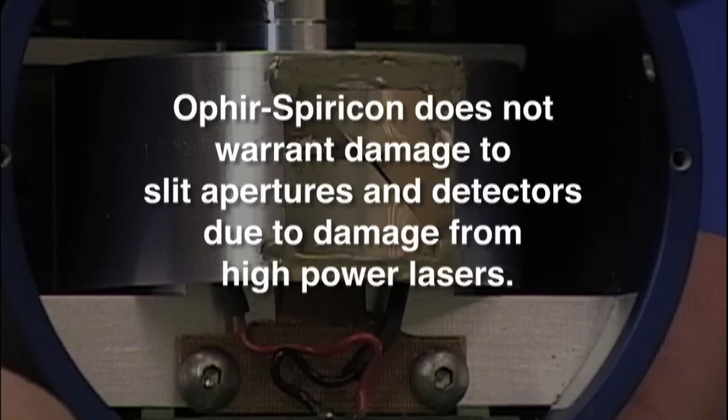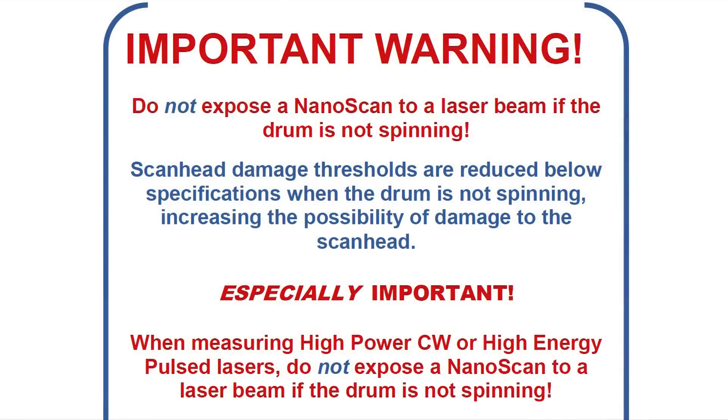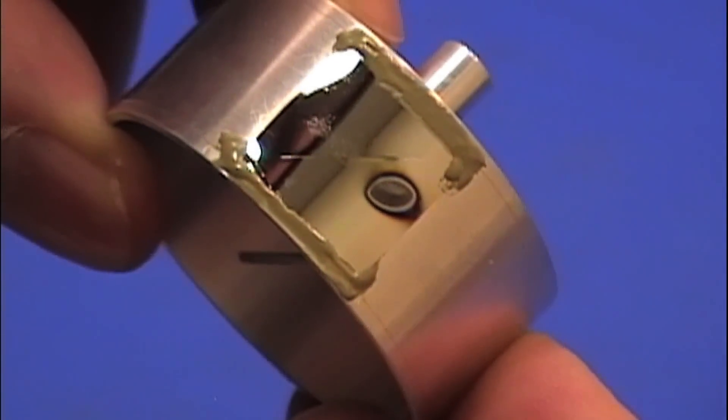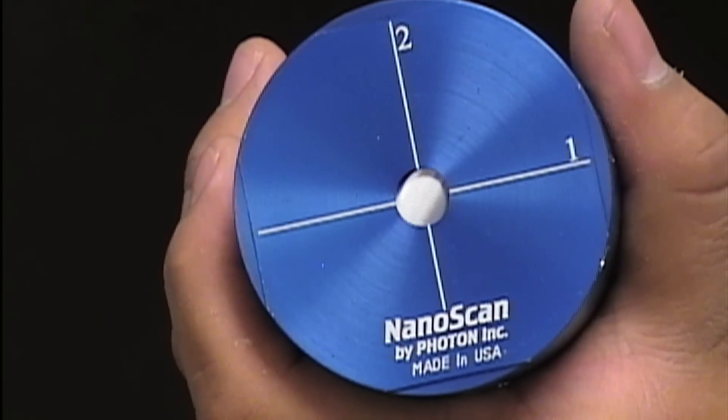Users of high-powered lasers must exercise caution when measuring their laser beams with their nanoscan. Damage to the slit apertures can occur at much lower power levels if the laser beam is directed into the slit apertures while the apertures are stationary. Always have the scanning profiler spinning when exposed to the laser beam.